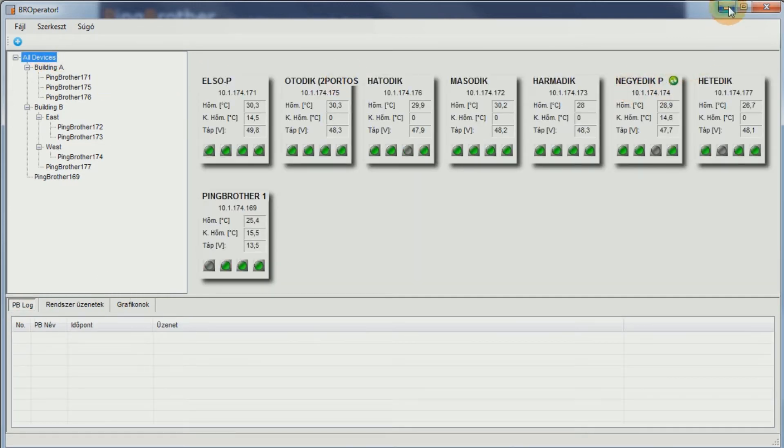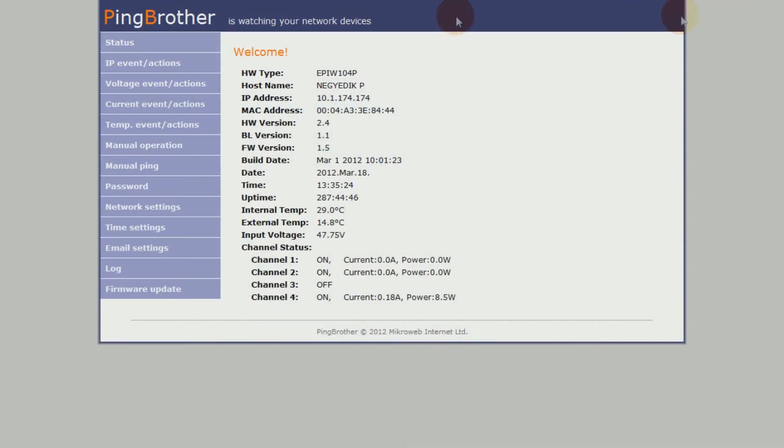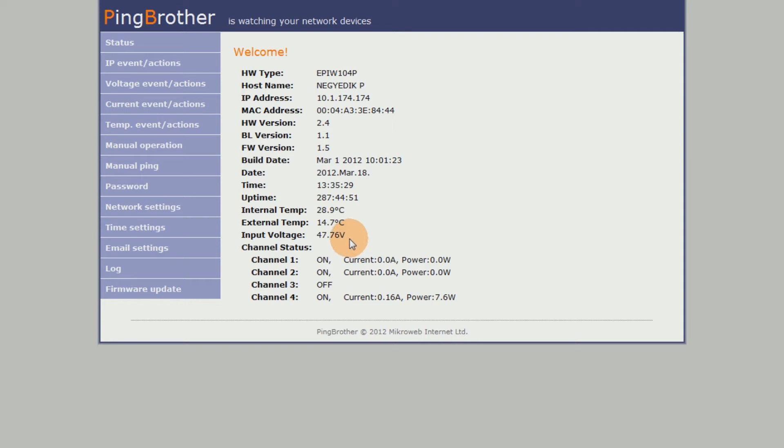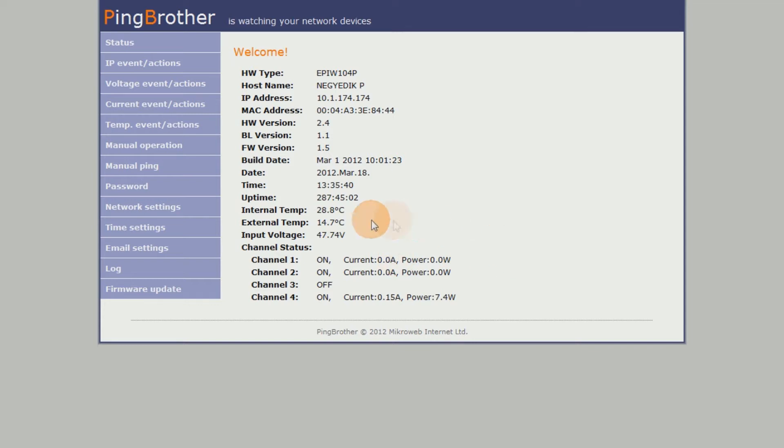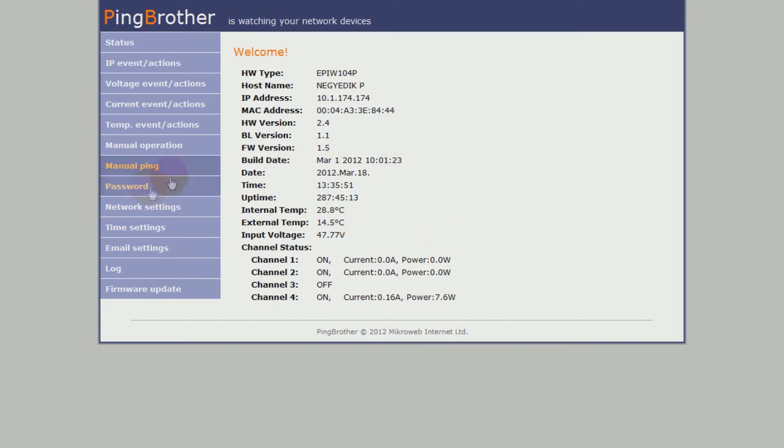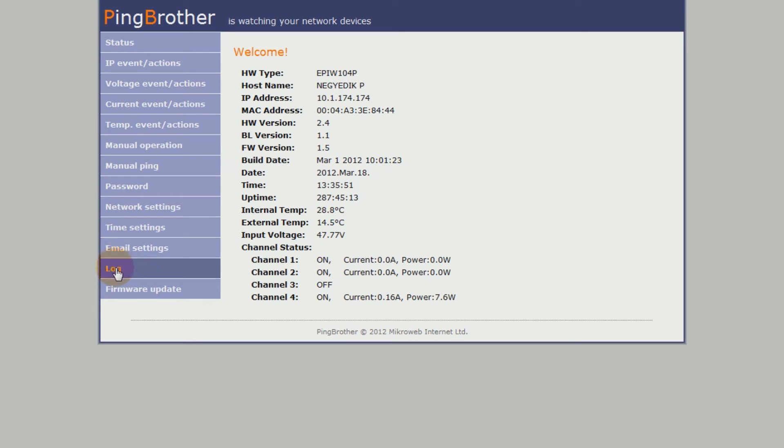In addition to displaying the date, time, uptime and other general information, the status screen provides readings of the voltage supplied to device and internal temperature, and for the EPIW-104P model only, the power consumption and output of PoE devices fed through the specific ethernet ports. You can also check the readings of an external temperature sensor provided as a default accessory to the EPIW-104 model. The system log window provides a clear overview of major system events, external user interventions, and the automatic watchdog responses of the device.